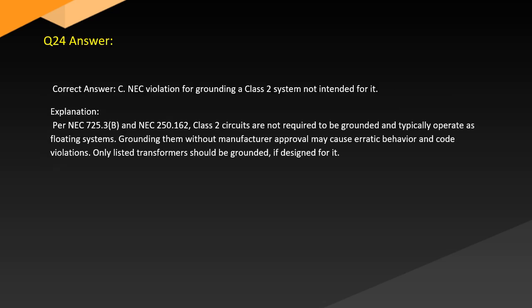Answer. Correct answer: C. NEC violation for grounding a Class 2 system not intended for it. Explanation. Per NEC 725.3(B) and NEC 250.162, Class 2 circuits are not required to be grounded and typically operate as floating systems. Grounding them without manufacturer approval may cause erratic behavior and code violations. Only listed transformers should be grounded if designed for it.